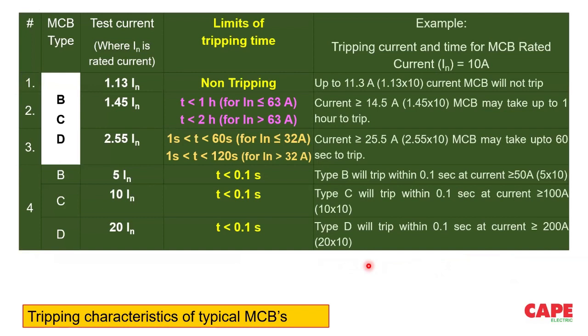OCPD, please keep in mind, there are 3 types of OCPDs available, B, C, D, MCBs, for example. MCB is a type of OCPD, and MCBs are of 3 types, B, C, and D. The difference of these devices is basically in the quick disconnection time. Quick disconnection time means instantaneous tripping time.